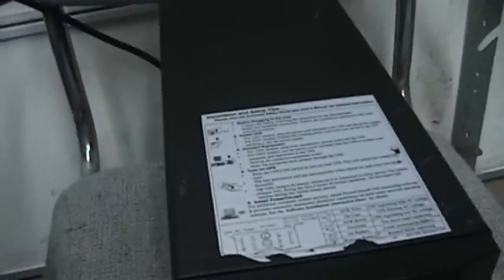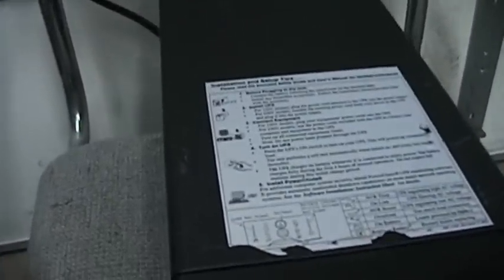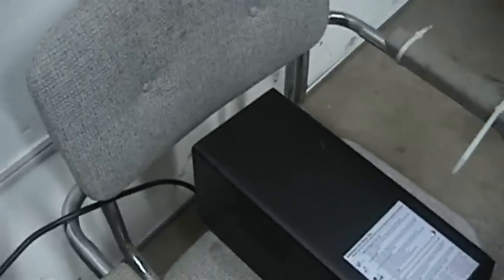This unit's a little interesting, as despite being only 500 volt amps smaller than the one you just saw, it hasn't actually got a cooling fan inside it. I really can't imagine it'll be too happy about being asked to deliver its full load. As I said, it's been my personal experience that a more lightly loaded UPS is much happier than one that's loaded to within an inch of its life.